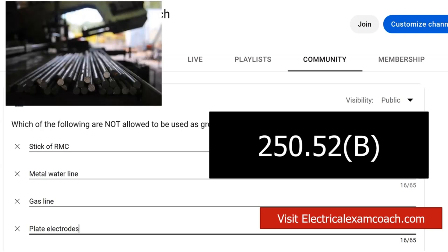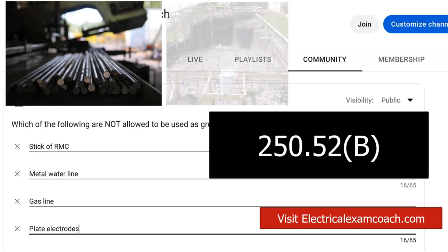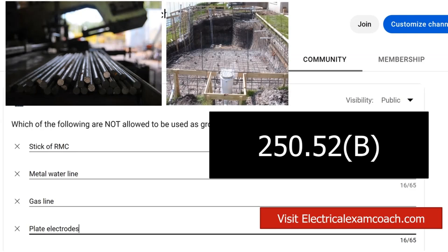The second one is anything like a pool, or a spa, or a whirlpool tub — nothing like that is allowed to be used as a grounding electrode system. Now there are proper ways to make the equipotential bond and to bond all of that out there at the pool, but we do not want to use that as a grounding electrode system. That's a lesson for another day.